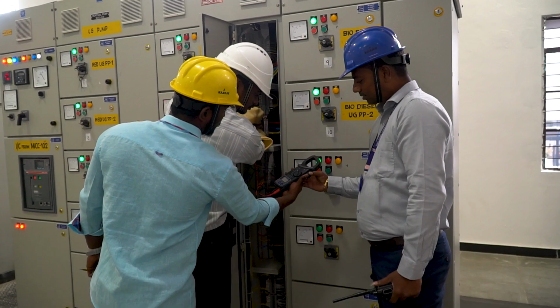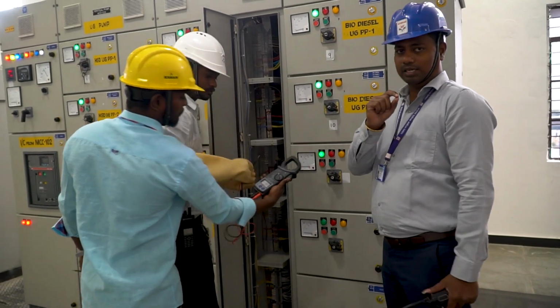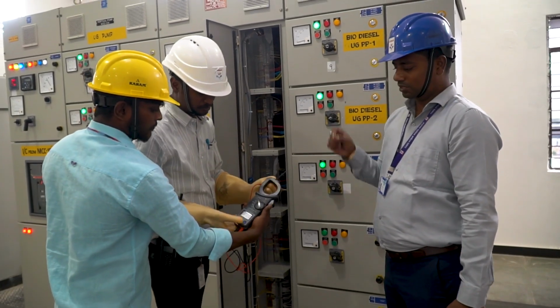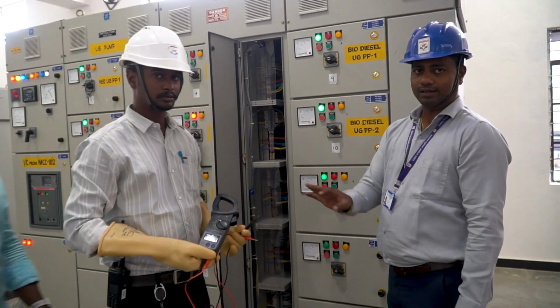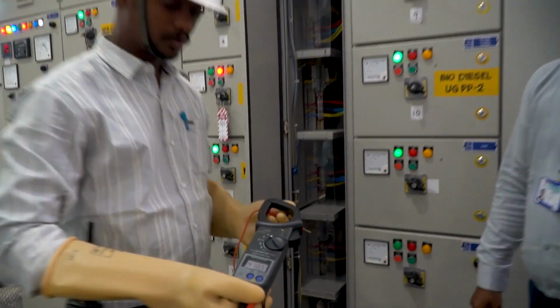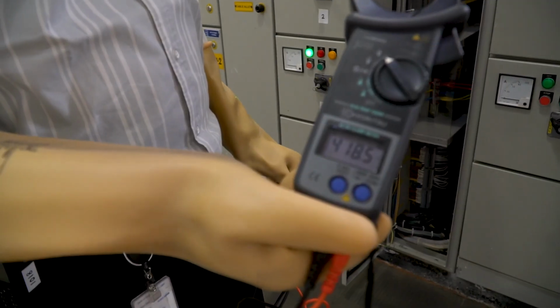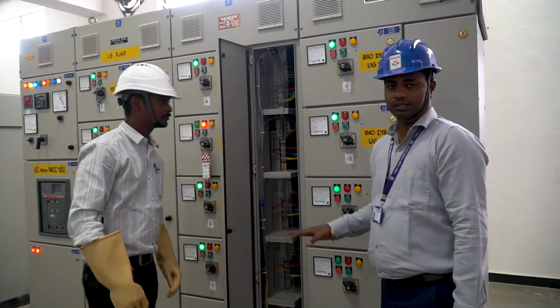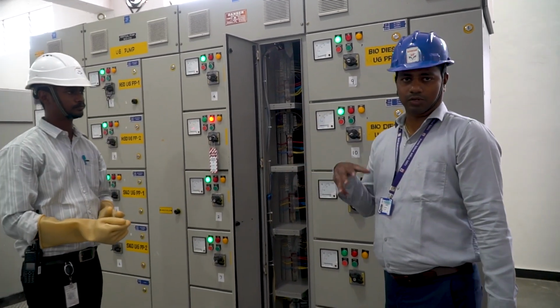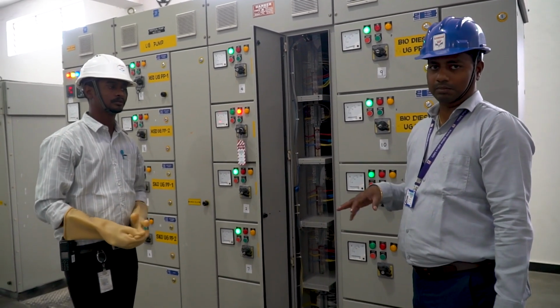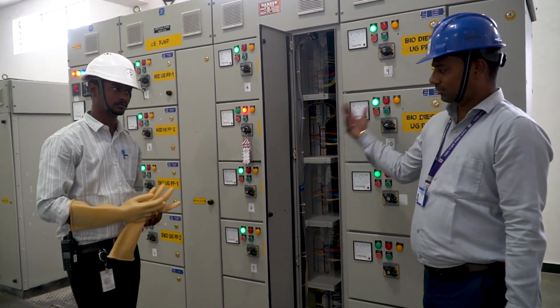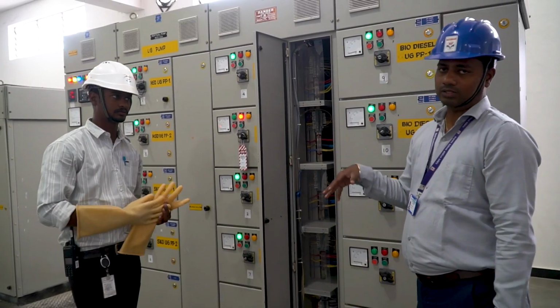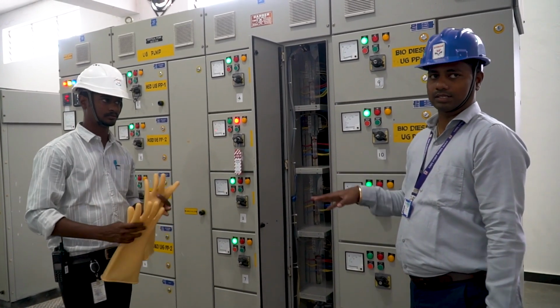So now we are checking the individual cable voltage level which is going to the UG pump, which seems to be an acceptable limit. 480. So the value we checked is correct and within the acceptable limit. So we can close the panel, remove the isolation tag and put the panel under usage.